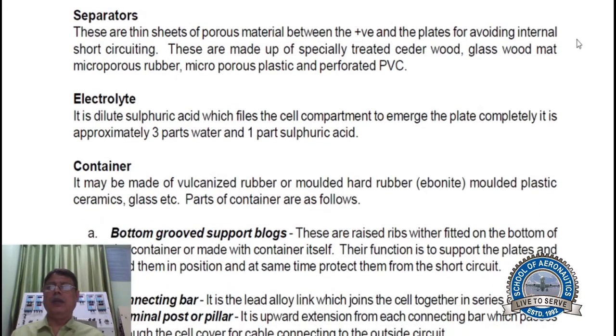Separator. These are thin sheets of porous material placed between the positive and negative plates to avoid internal short circuiting. These are made of specially treated cedar wood, glass wool, mat, micro porous rubber, micro porous plastic, and PVC.